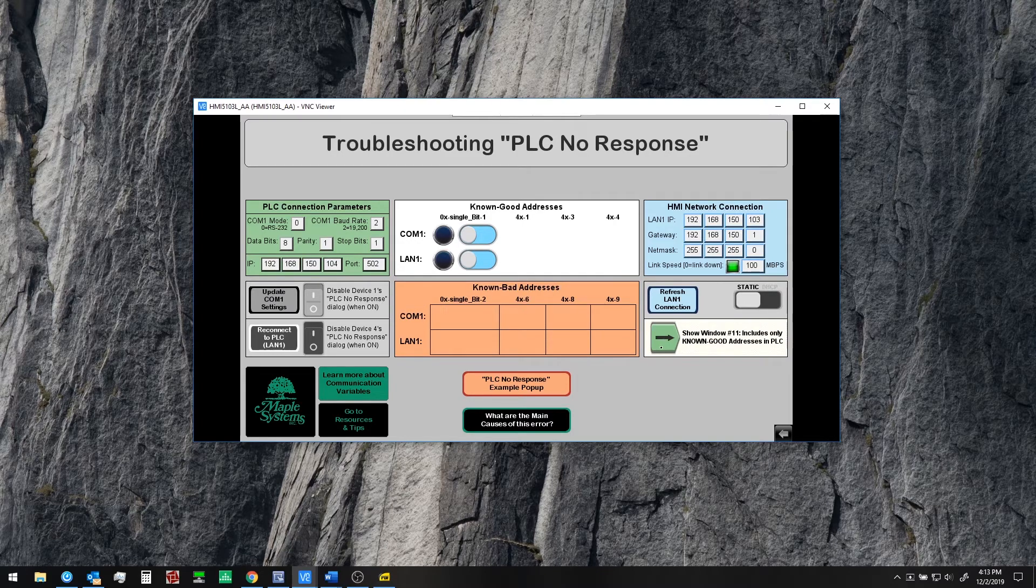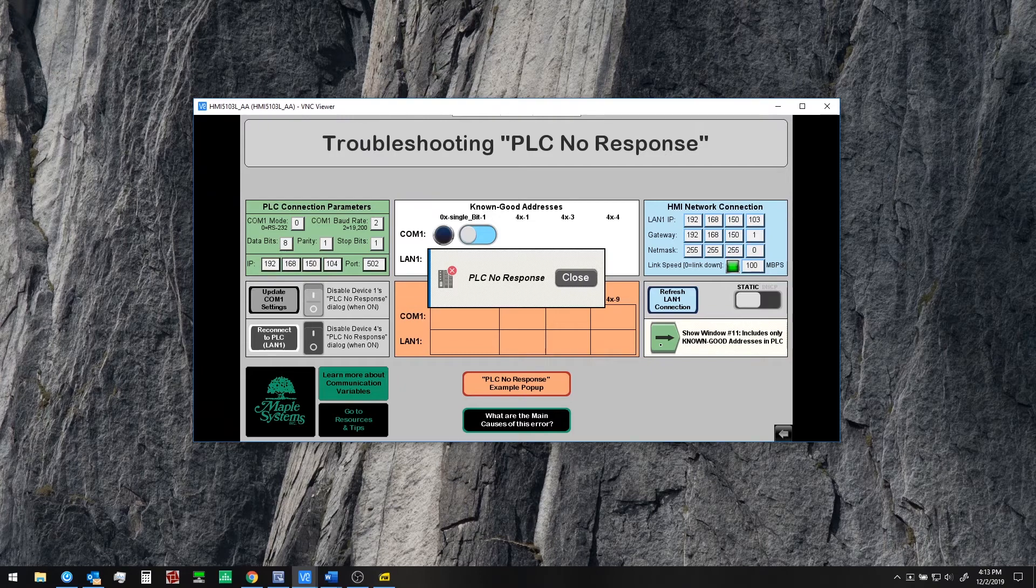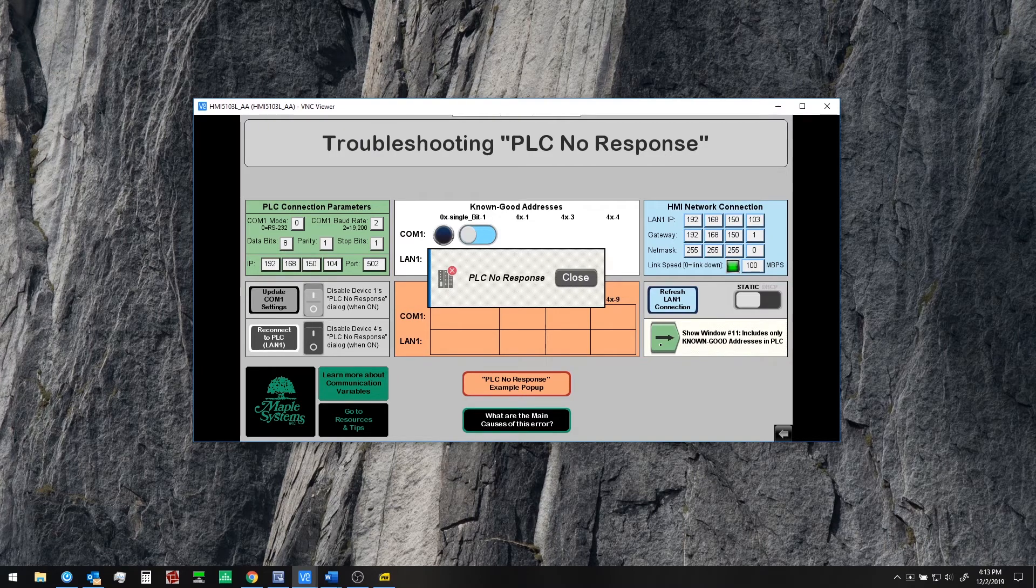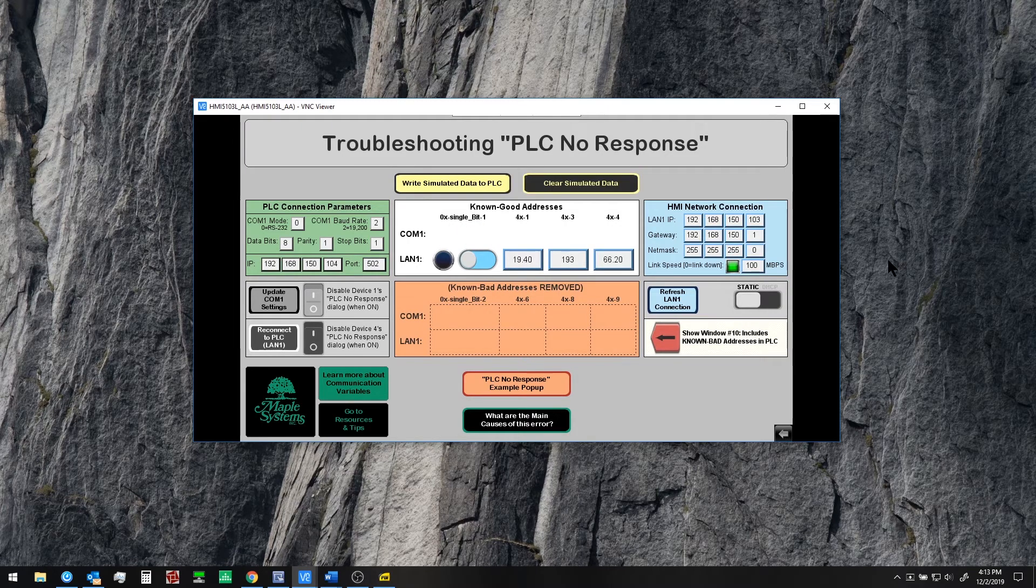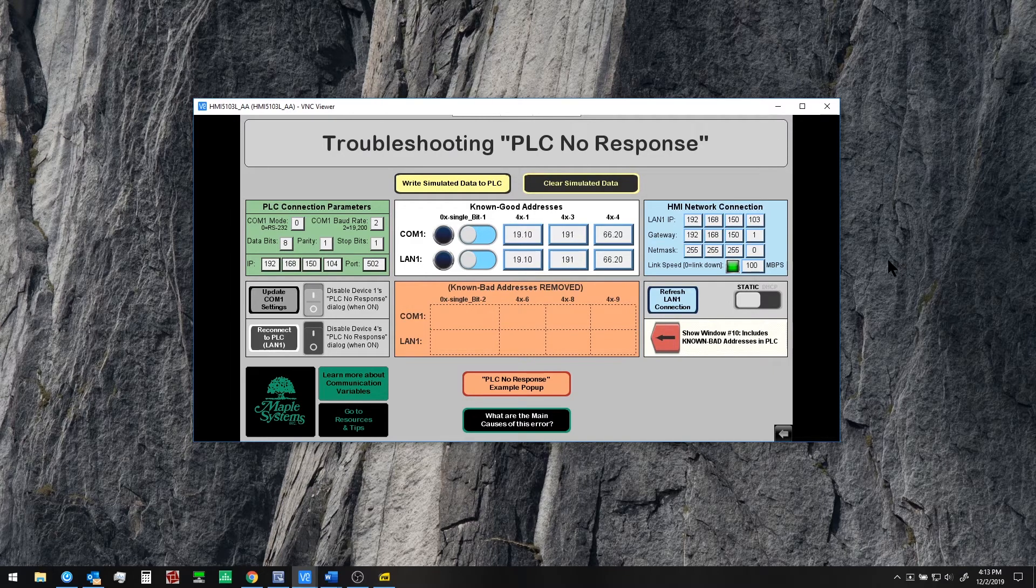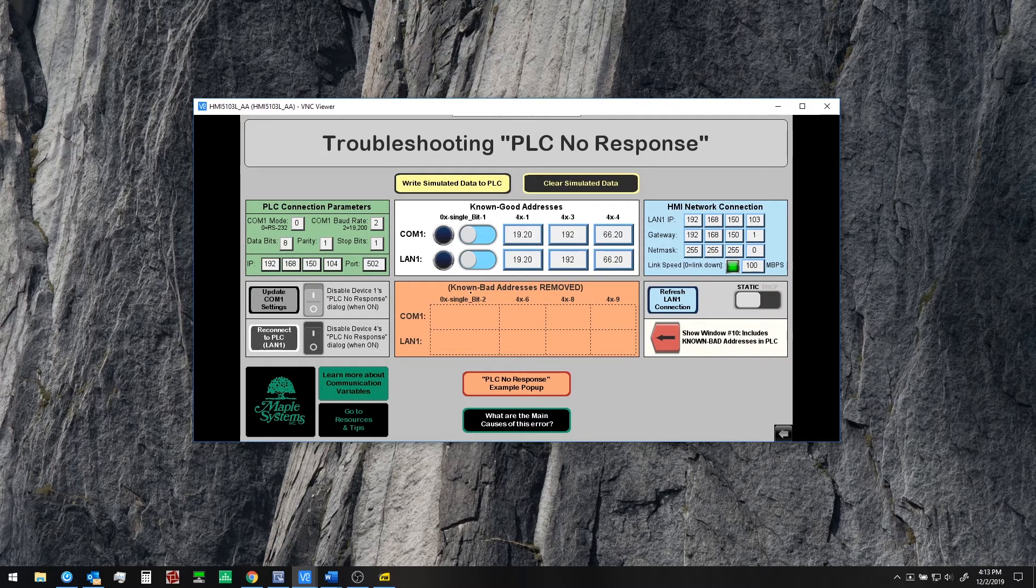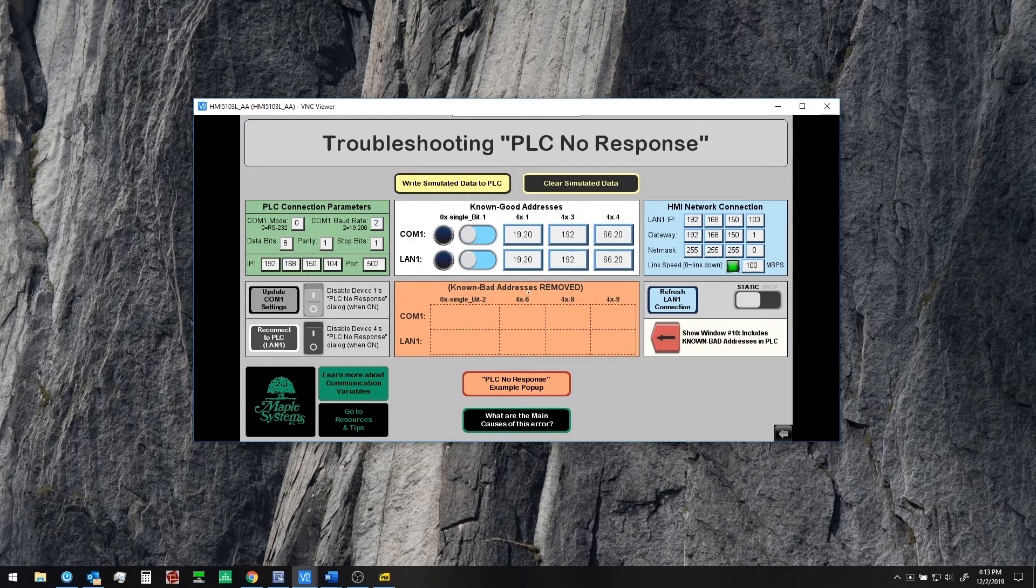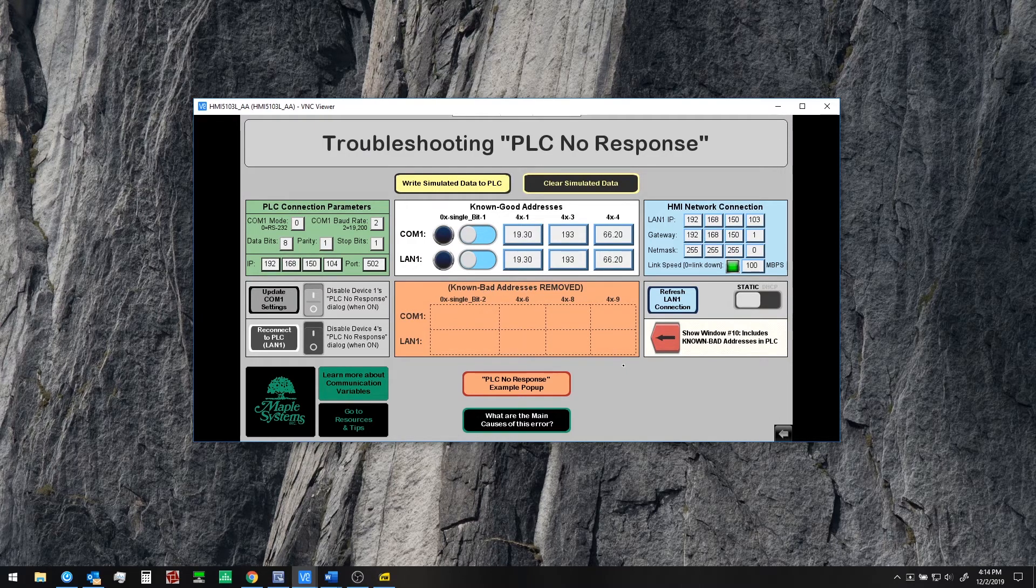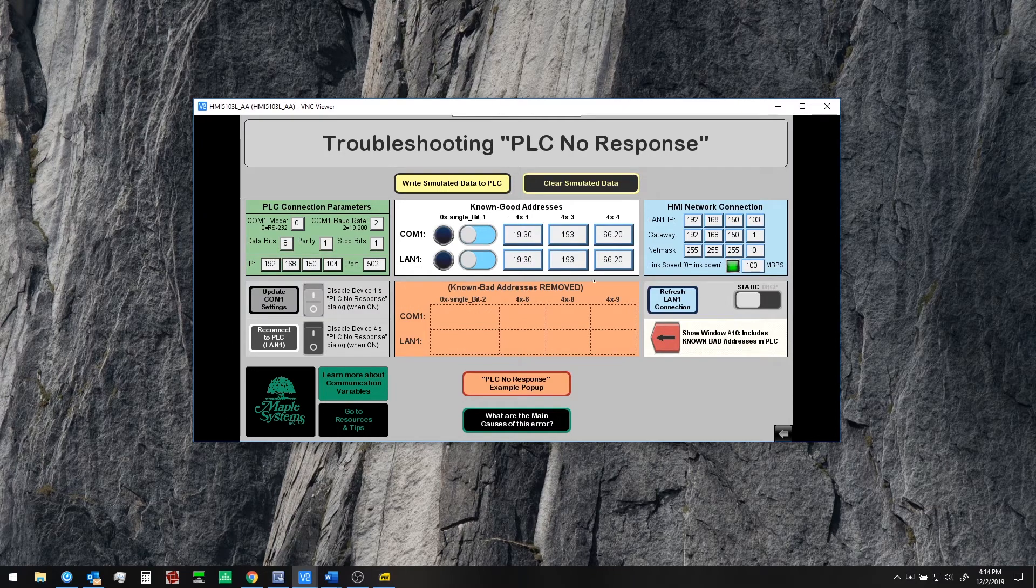If we go now to our window number 11 this includes only known good addresses in the PLC. Now we can see these objects appear and we're reading the values from the PLC in real time. So what's the difference? Here we've removed the known bad addresses or objects including known bad addresses from this window. Just by doing this we now see all of this data coming in.